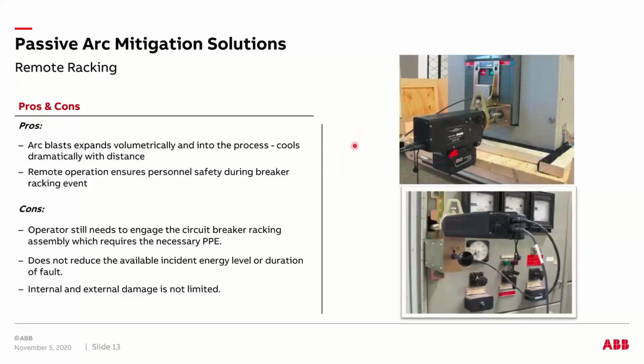Similarly, for a remote racking device, it's very well known that the arc blast expands volumetrically. So the farther away the operator is from the equipment, the safer it is for them to operate the equipment, whether it's racking in or racking out a breaker. But on the other side, some of the disadvantages include that you're not really reducing the available incident energy levels. Rather, you are putting the operator outside of the zone of blast. So you are definitely protecting your personnel, but there is some significant damage that could occur within your equipment.